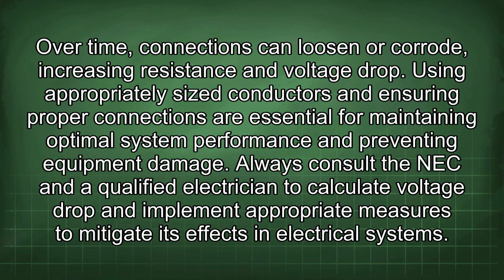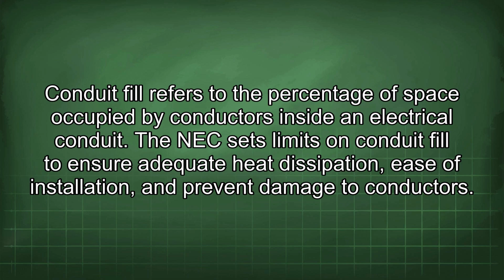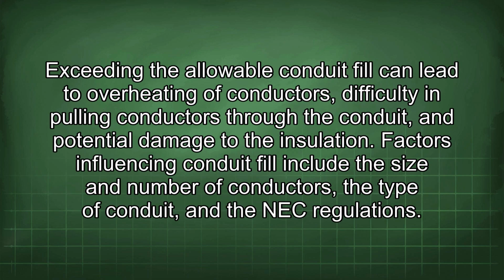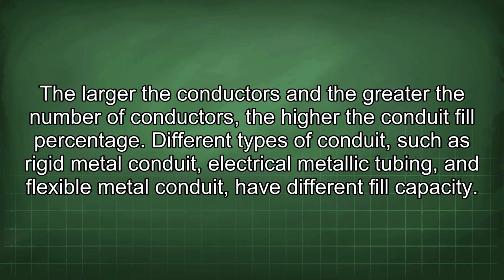Conduit fill refers to the percentage of space occupied by conductors inside an electrical conduit. The NEC sets limits on conduit fill to ensure adequate heat dissipation, ease of installation, and prevent damage to conductors. Exceeding the allowable conduit fill can lead to overheating of conductors, difficulty in pulling conductors through the conduit, and potential damage to the insulation. Factors influencing conduit fill include the size and number of conductors, the type of conduit, and the NEC regulations. The larger the conductors and the greater the number of conductors, the higher the conduit fill percentage.